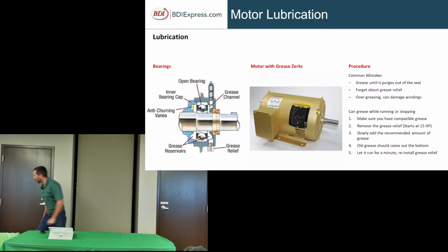I'm going to step away here, but on the shaft end of the motor, and then towards the back where the fan is, there's going to be your grease zerks, and then right below those, you're going to have the grease reliefs. But make sure that you remove those grease reliefs, and then you want to grease. Some common mistakes: greasing until the grease purges out of the seals. Most of your bearings on a motor are not visible, so that grease is purging out and going into your motor windings.